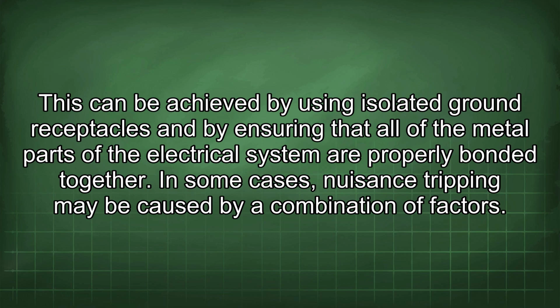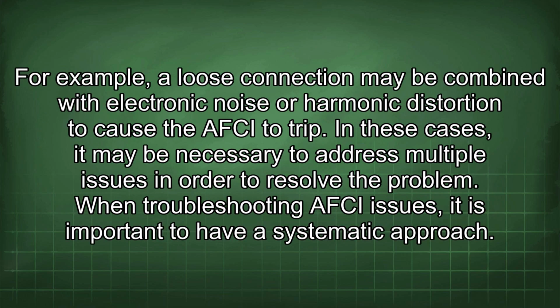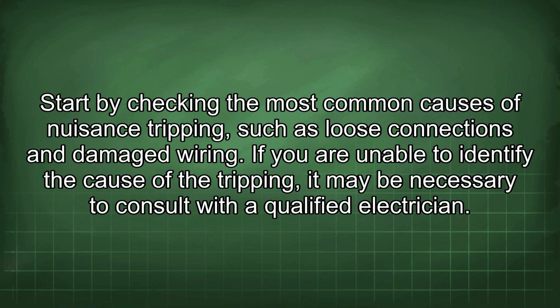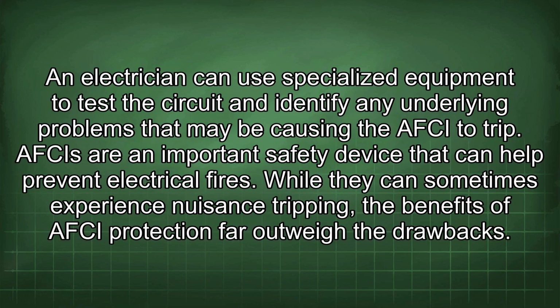In some cases, nuisance tripping may be caused by a combination of factors. For example, a loose connection may be combined with electronic noise or harmonic distortion to cause the AFCI to trip. In these cases, it may be necessary to address multiple issues in order to resolve the problem. When troubleshooting AFCI issues, it is important to have a systematic approach. Start by checking the most common causes of nuisance tripping, such as loose connections and damaged wiring. If you are unable to identify the cause of the tripping, it may be necessary to consult with a qualified electrician. An electrician can use specialized equipment to test the circuit and identify any underlying problems that may be causing the AFCI to trip.